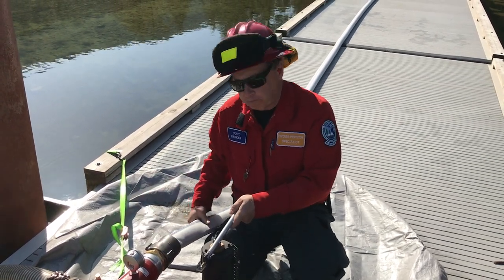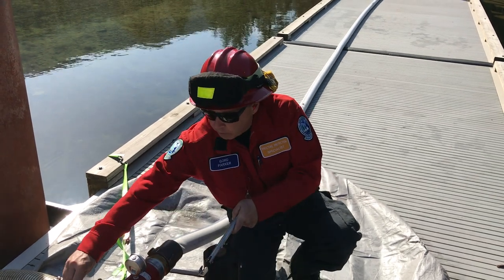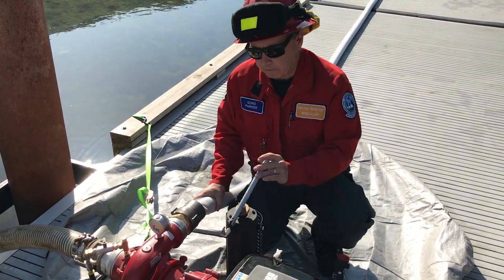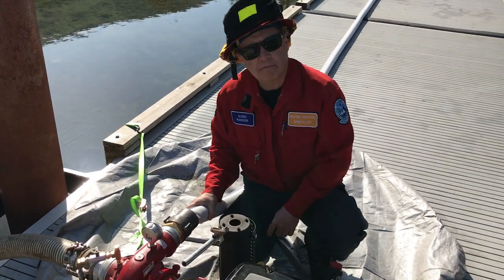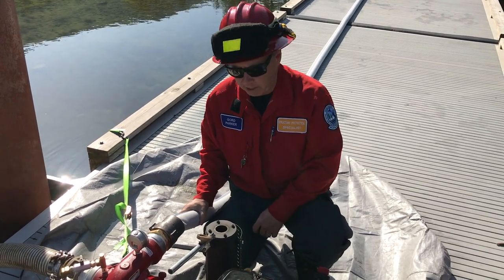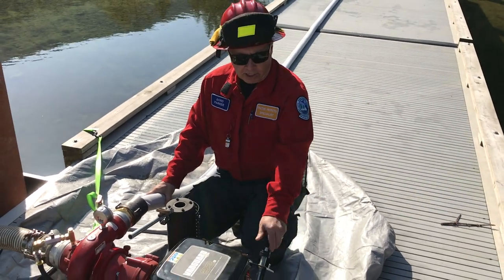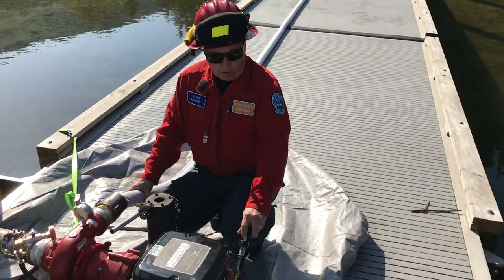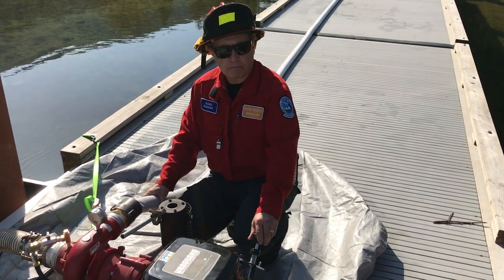water through the discharge end of the pump into the hose, then we're going to slowly close off our priming valve, and then we're going to release the handle off of the top of the exhaust and allow the motor to run properly. And then what we'll do is we'll start to adjust our motor RPM with the throttle here, and work at the desired pressure.